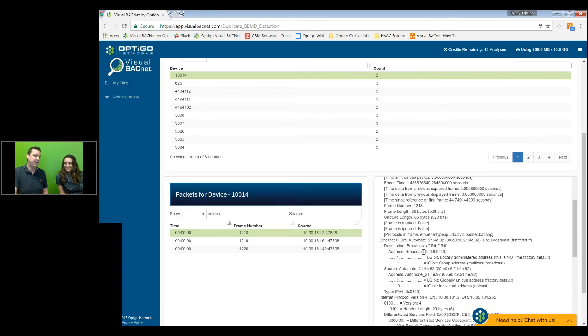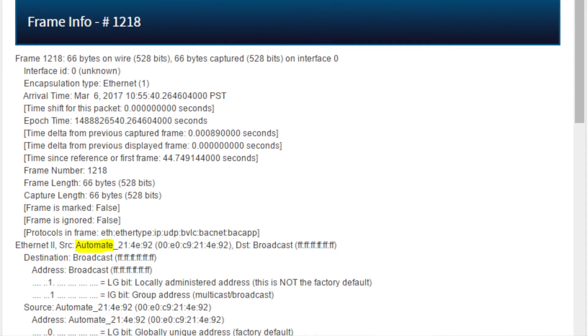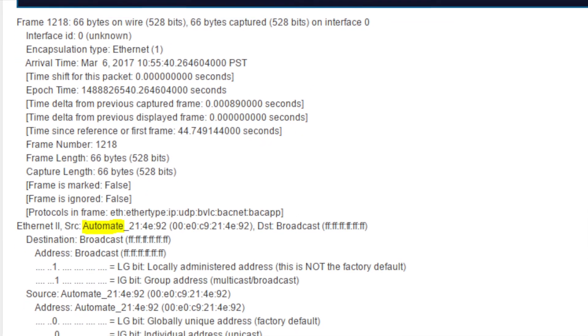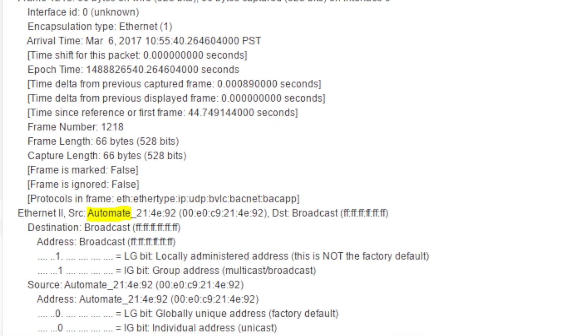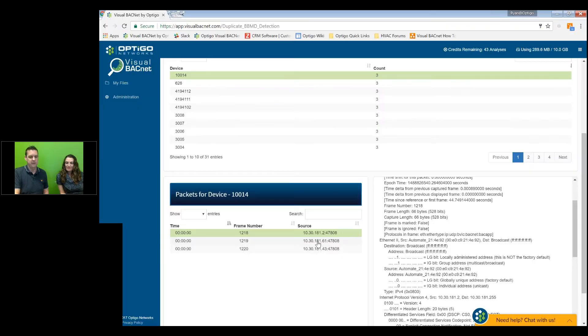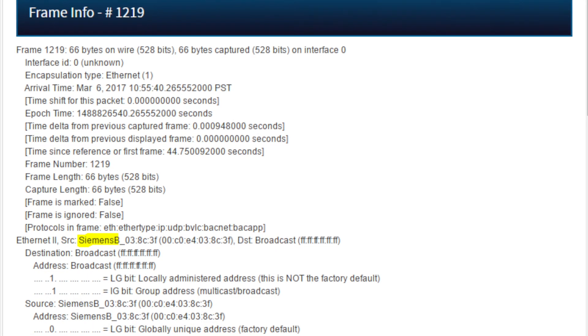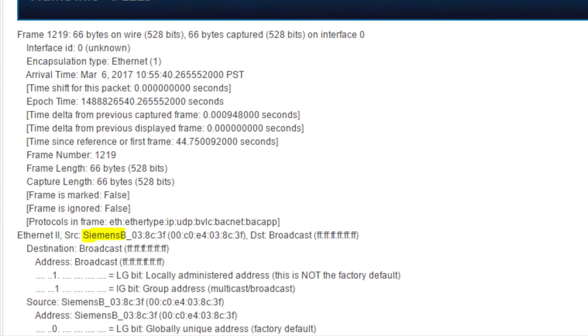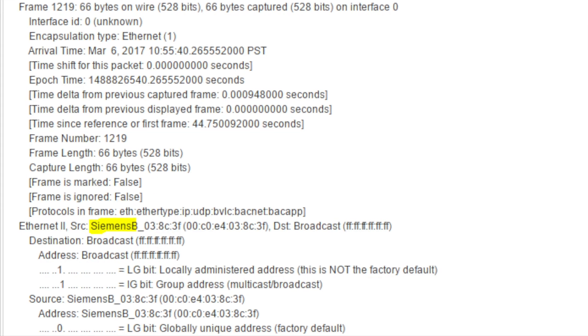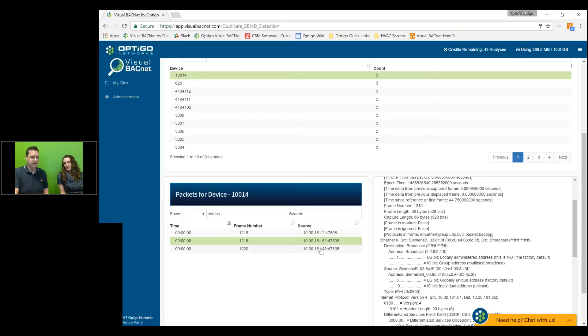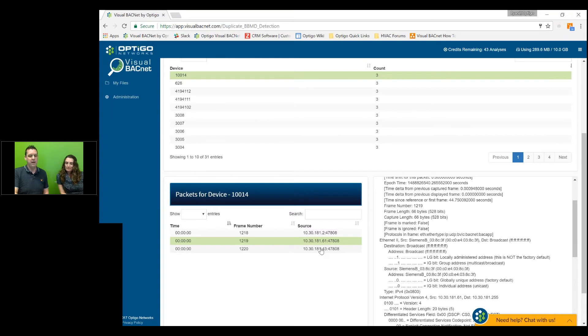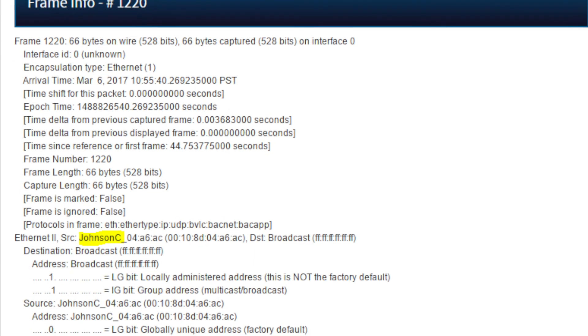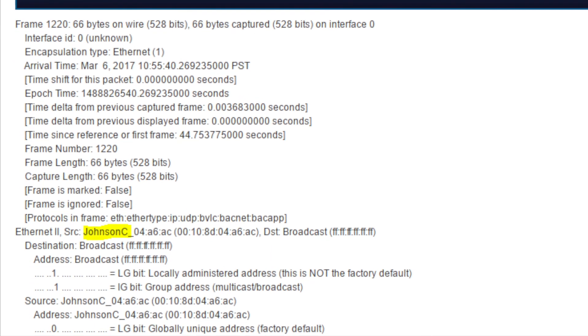It's not that scary. We can step right in and you can see here the first device is by Automated Logic. So IP address, Automated Logic device. Second device is Siemens. Siemens has also added a BBMD. So that information is available from the MAC address. Right. And we'll check the last device. There's a Johnson controller here as well. It's also a BBMD.